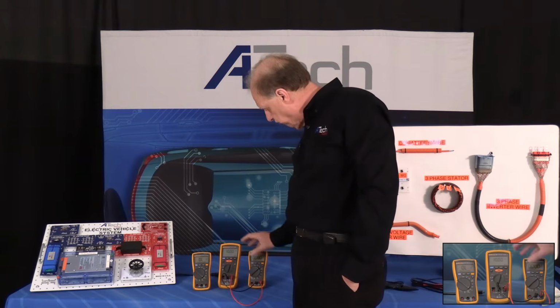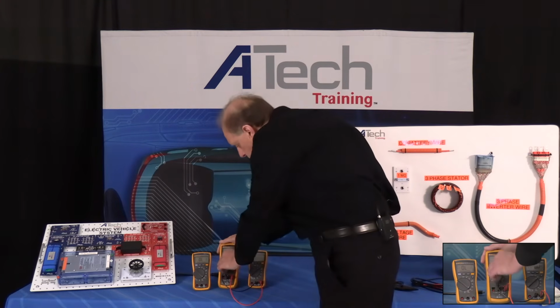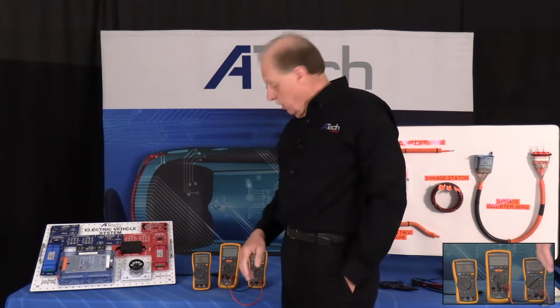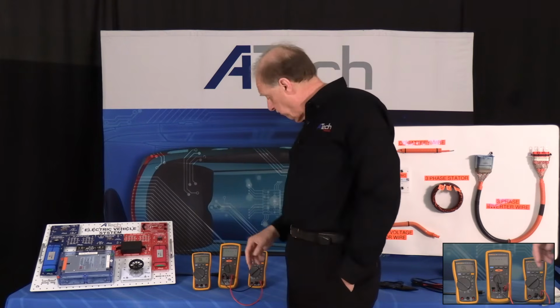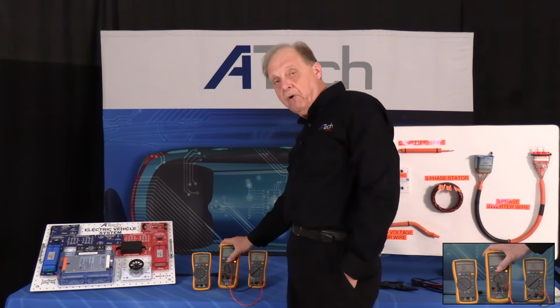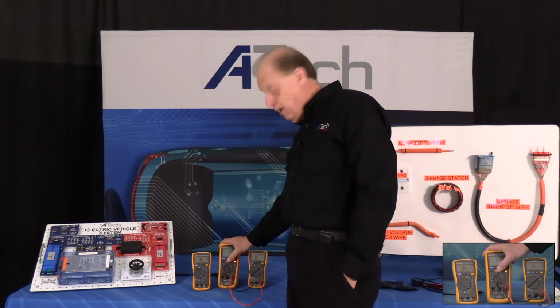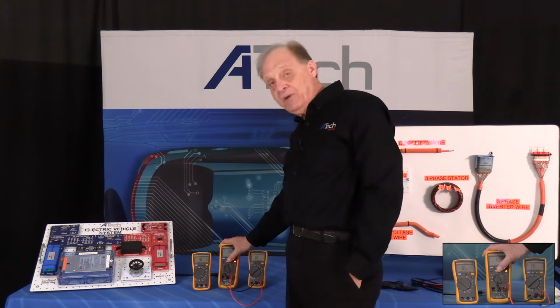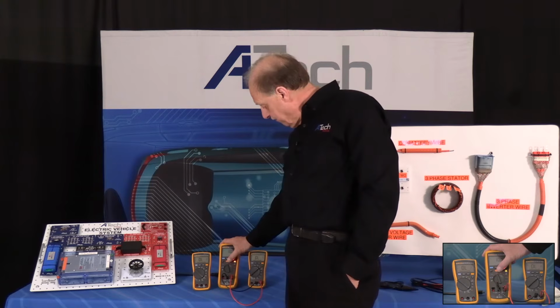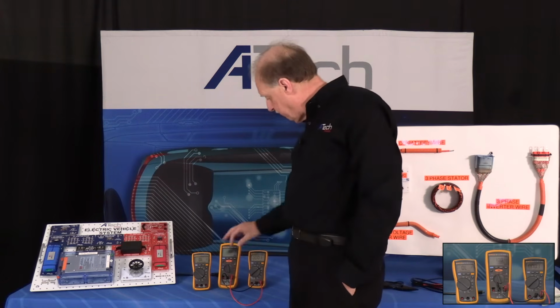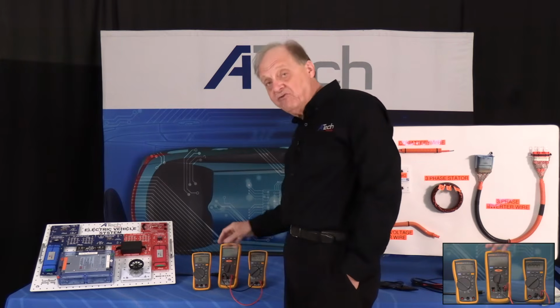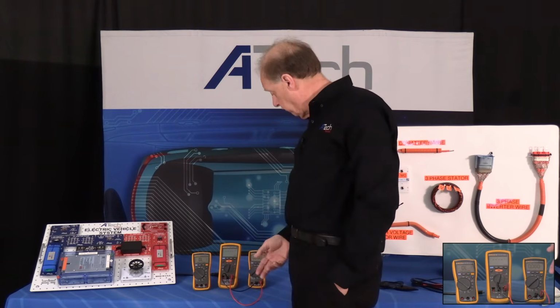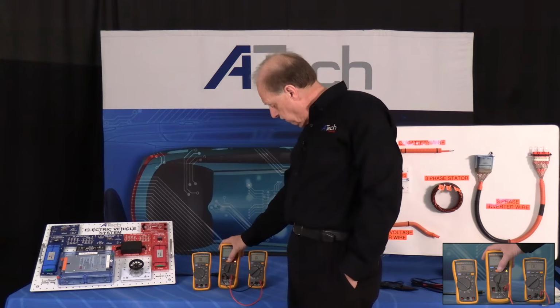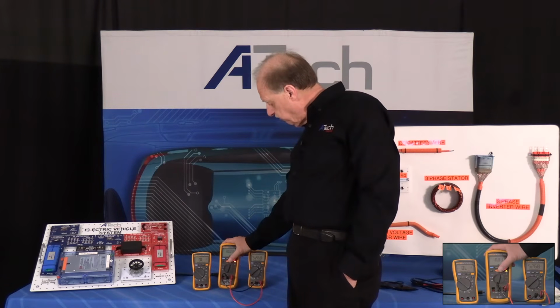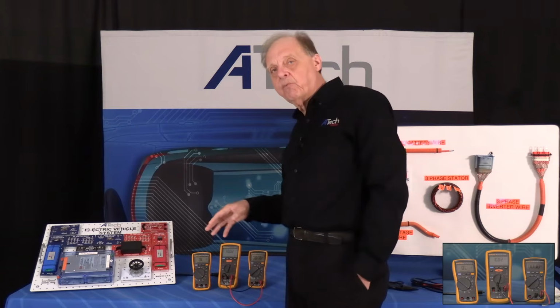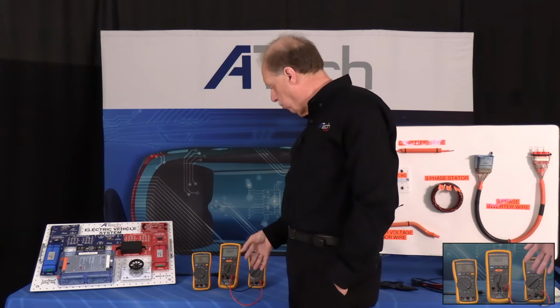Now watch what happens when I turn this meter up to 1,000 volts. Because we will do some testing at that point, I put it there, and it just goes overload, out of limits, out of luck, depending on how you look at it. Some meters will say 'ouch.' This one is just telling me I don't have the range in this particular meter to handle that kind of voltage. Again, at 500 volts you'll see it measure back and forth. So in other words, we're testing the meter out to see if it's working properly.